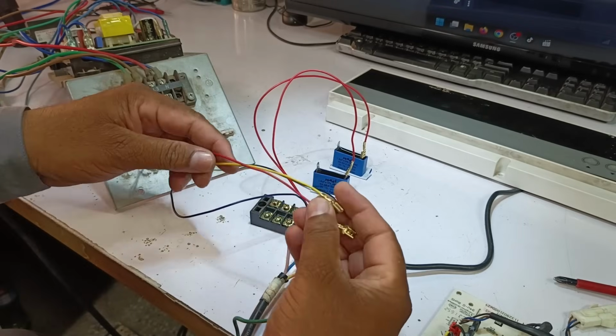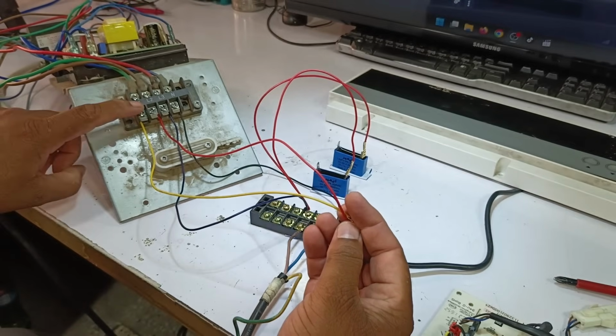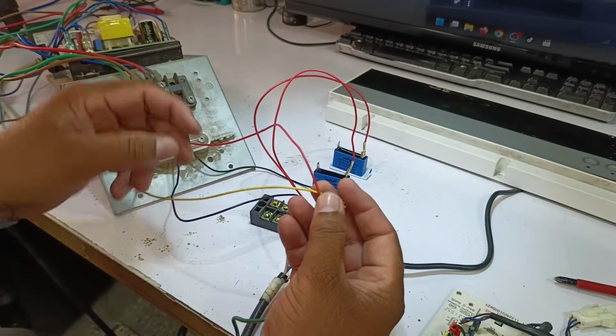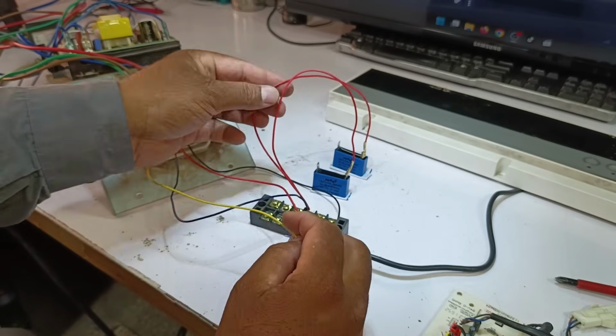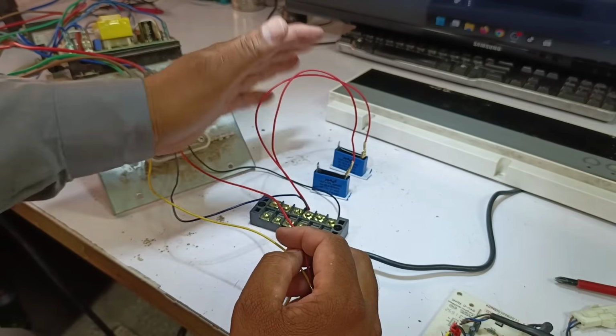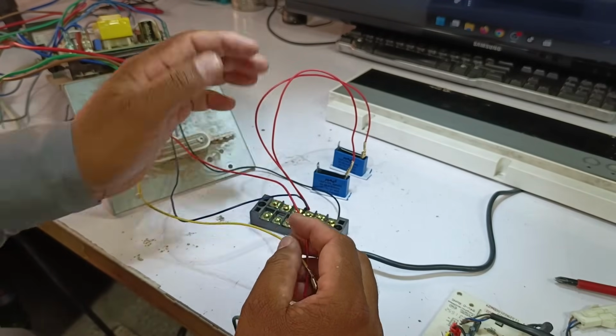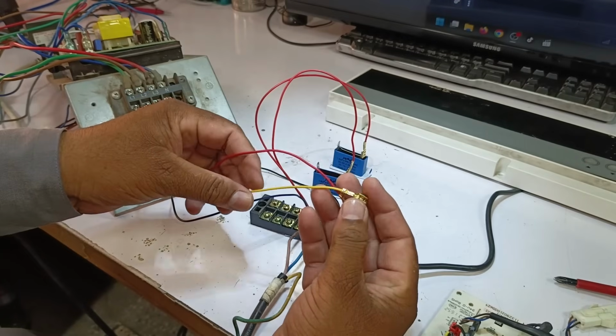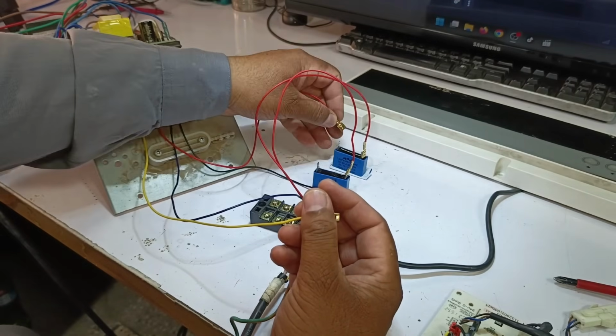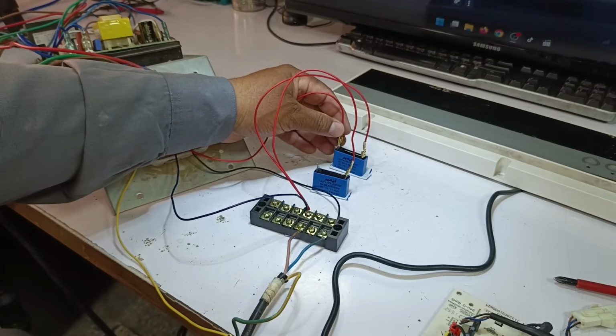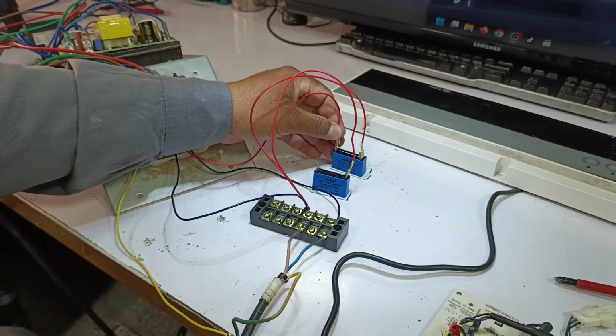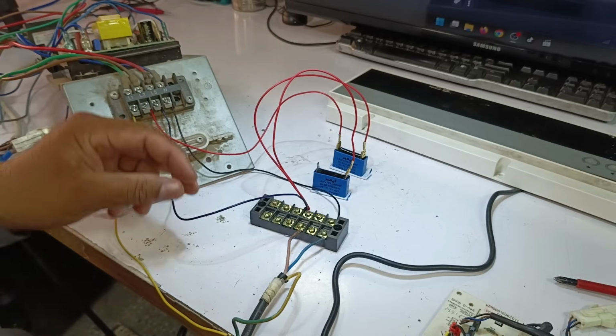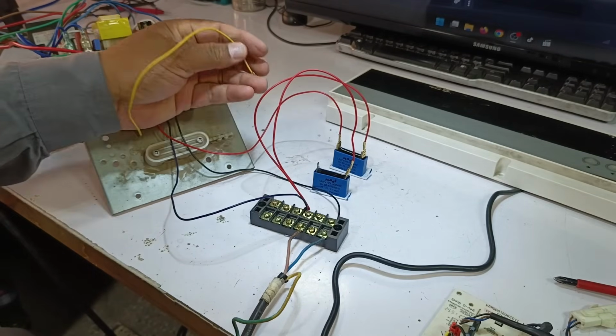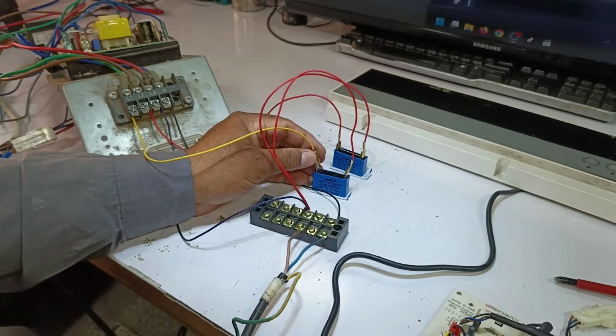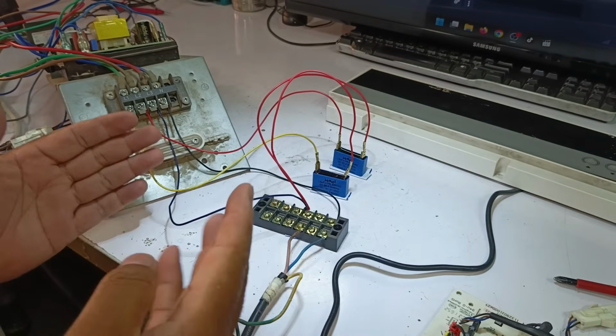Now, the wires we previously connected to the outdoor PCB terminal need to be connected as well. At this stage, phase polarity is not important. We only need a phase signal. So, you can connect any of the 2 wires to either capacitor. I will connect the red wire to this capacitor here. We are only using this setup for phase detection purposes, so the red wire has been connected. Now, we will connect the yellow wire to the other connector of the second capacitor. With this, our fake 3-phase supply is now ready.